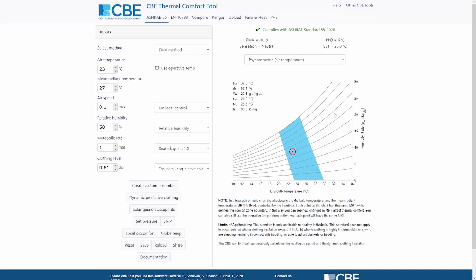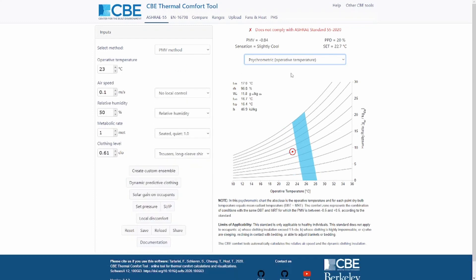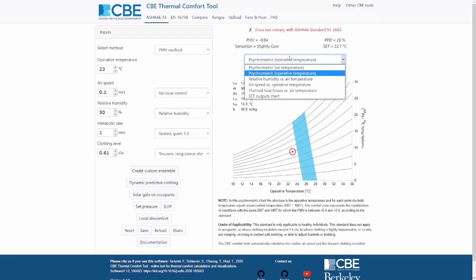This is, in many cases, wrong, because you will hardly find a space which is at 14 degrees air temperature and yet has a mean radiant temperature of 27 degrees. Of course it's up to you to choose whichever chart you want to use, but I just wanted to highlight that. That's why we set as the default the psychrometric with the operative temperature, which combines the dry bulb and the mean radiant temperature.